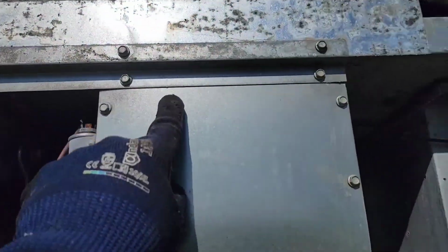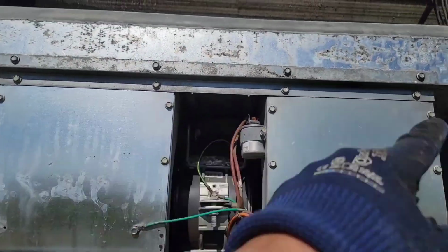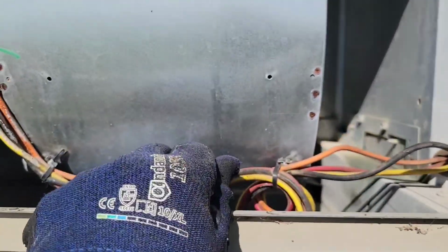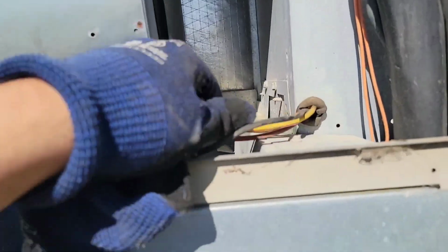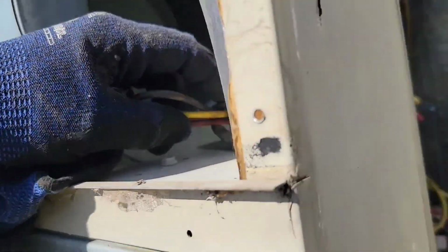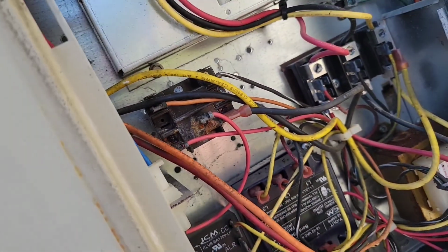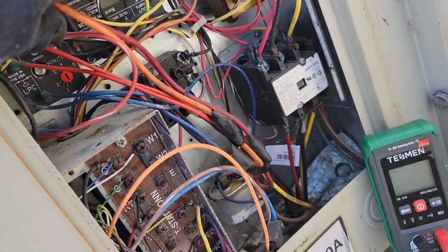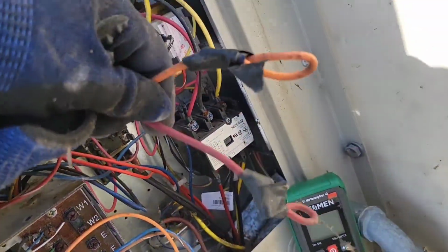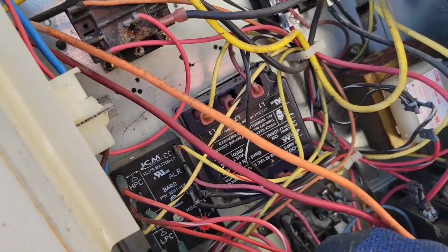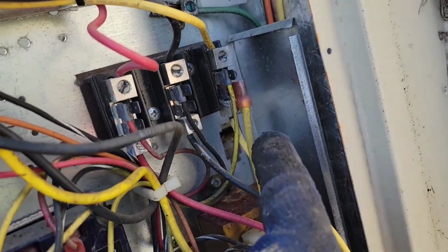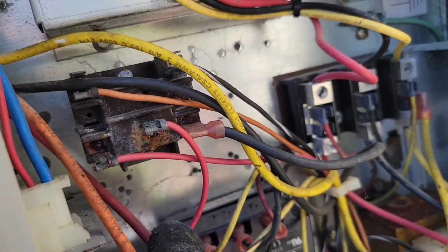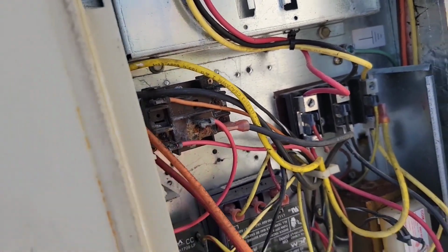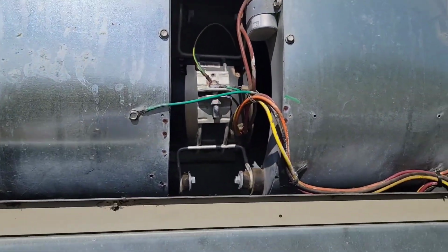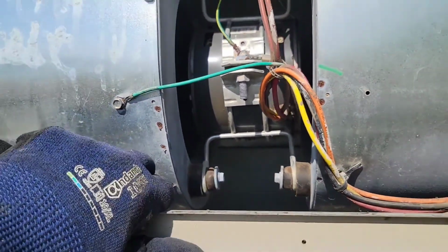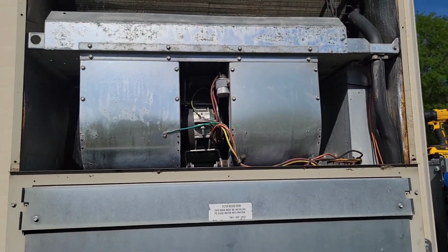So you got 1, 2, 3, 4, 5, 6, 7, 8, 5/16 screws. You take those loose, and then you can probably just cut the wire right here, wire nut it back together, or come right here, find where the wires go, and then you can just take them all out. Just make sure you know exactly where they go. You can see some of the speeds are not being used for that blower motor. You've only got a yellow wire going to one side of the power, and then a black wire going to this relay. This is a relay that controls that blower. So we got a little blower relay there. But they do go bad, and you can see a little bit of oil from this motor. So just want to show you that.